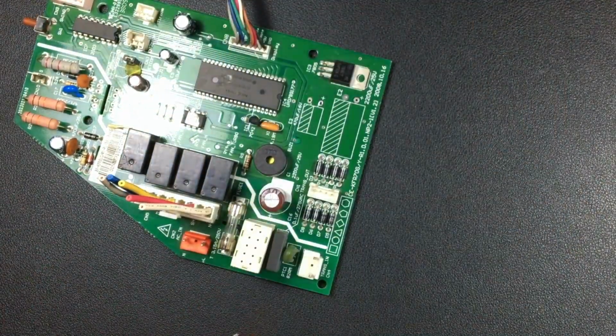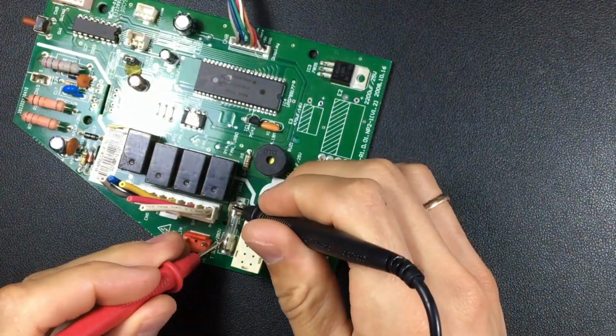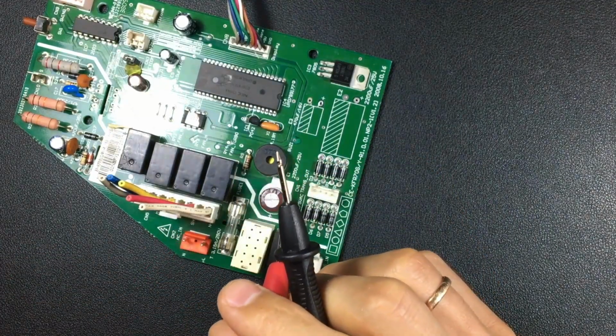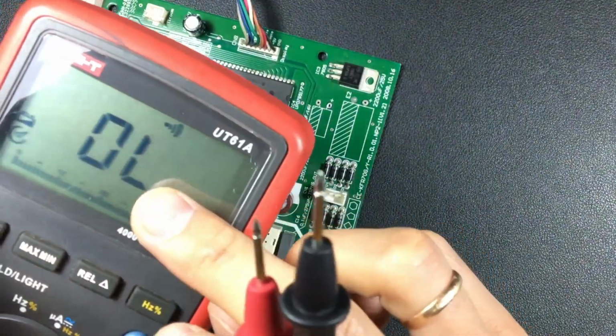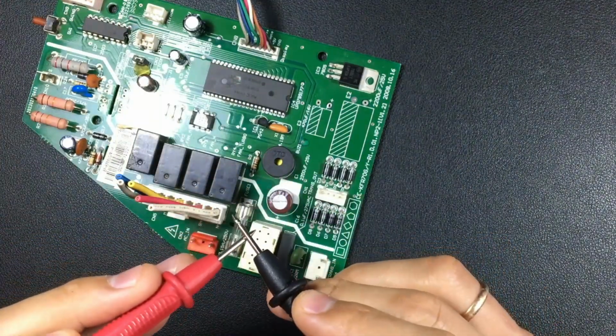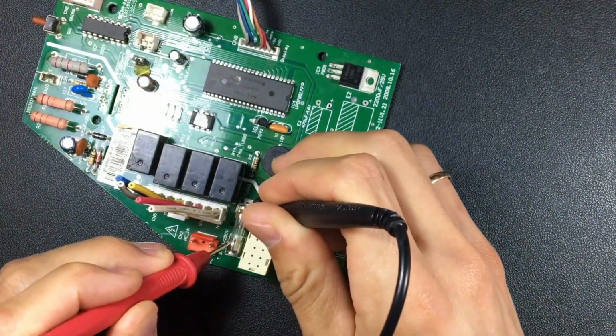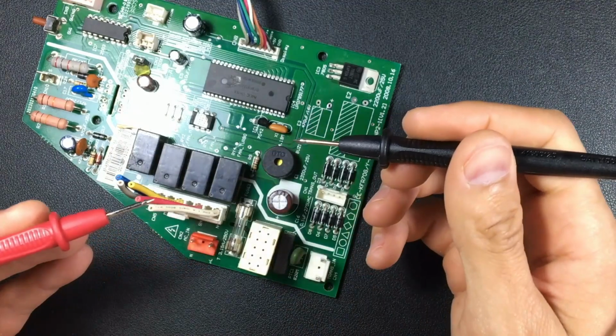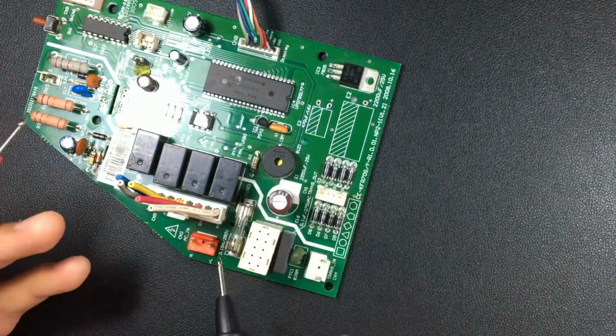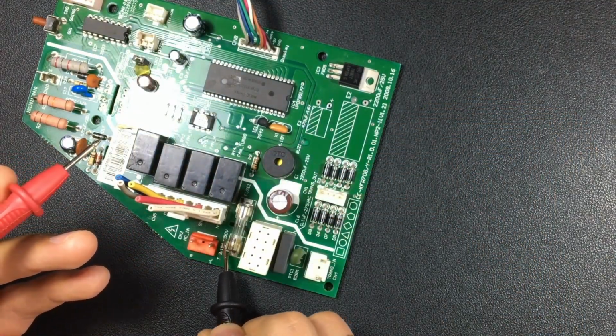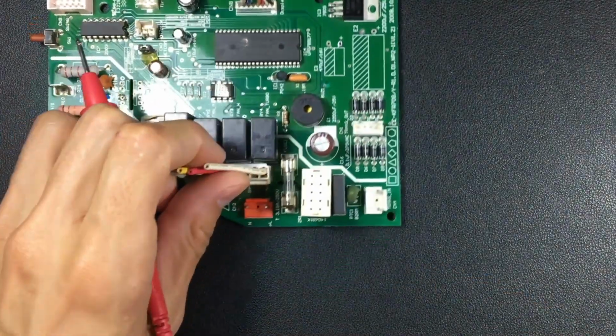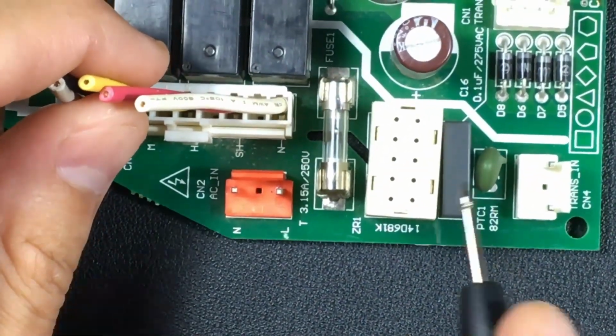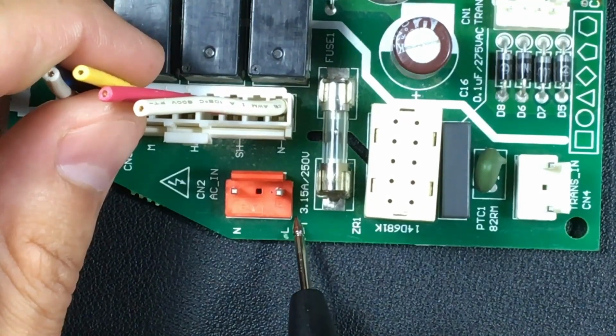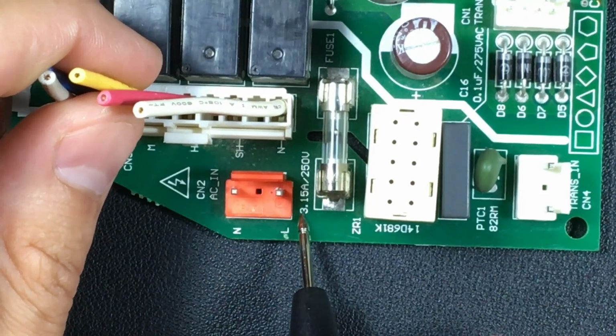Regarding the fuse, which is also part of this circuit, the fuse has to have direct continuity. We can put the multimeter in the sound function so that it sounds when continuity is made, and there just has to be continuity. If it is going to be replaced, it must be replaced with one of the same voltage and the same amperage as the one it originally had. Here we can see the values of the fuse printed on the electronic board.